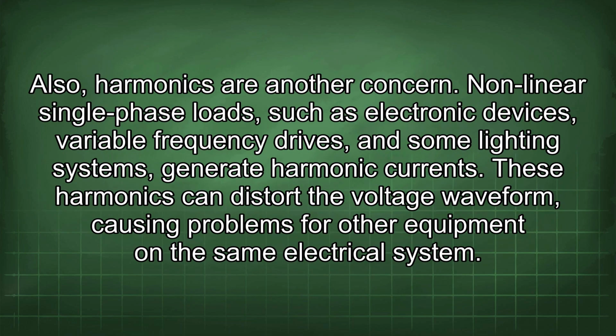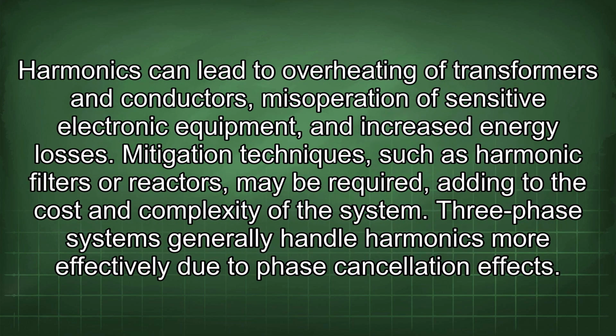Also, harmonics are another concern. Nonlinear single-phase loads, such as electronic devices, variable frequency drives, and some lighting systems, generate harmonic currents. These harmonics can distort the voltage waveform, causing problems for other equipment on the same electrical system. Harmonics can lead to overheating of transformers and conductors, misoperation of sensitive electronic equipment, and increased energy losses. Mitigation techniques, such as harmonic filters or reactors, may be required, adding to the cost and complexity of the system. Three-phase systems generally handle harmonics more effectively due to phase cancellation effects.